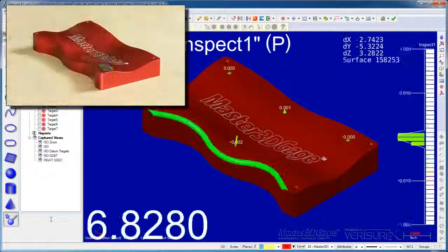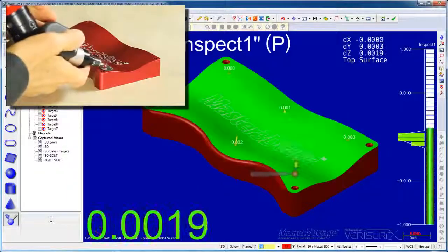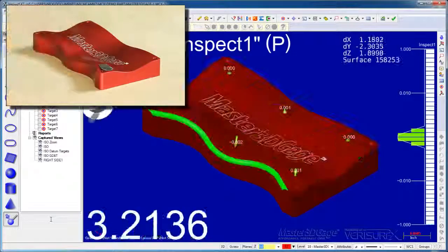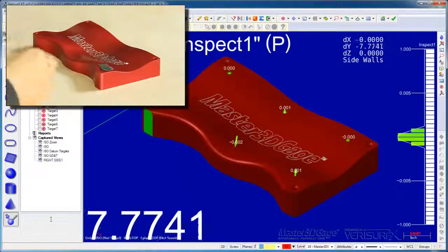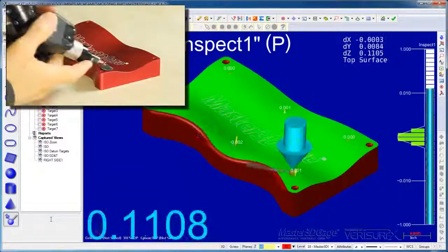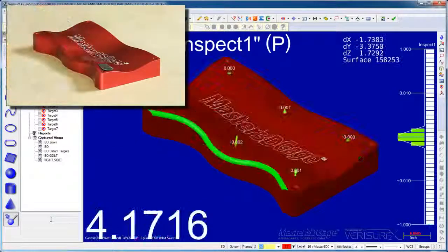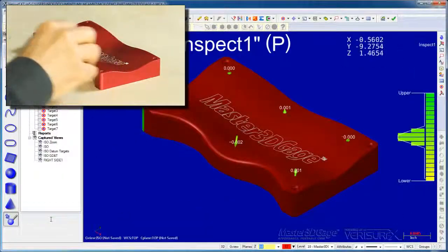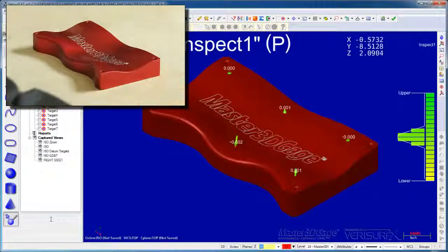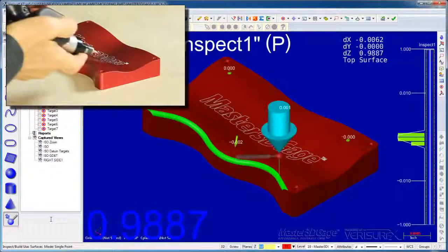If I shim the surface and place the probe on top, notice that the build arrow points down. When I record the deviation, the arrow points up. That's because the build arrow shows where the surface is supposed to be, and the deviation arrow shows where it actually is. I'll undo that point and remeasure it without the shim.